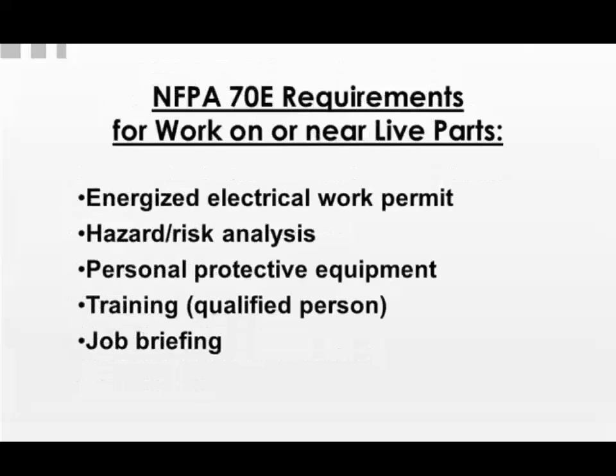So for NFPA requirements for work on or near live electric parts, you have to have an energized electrical work permit. You have to conduct a hazard risk analysis with all the parties involved. You have to make sure you have the right personal protective equipment on. You have the right training, so a qualified person, and you have to do a job briefing. So a lot of steps need to be involved and should be involved. Don't shortcut any of these steps. Not only are you violating the consensus standard, but you're putting your employees at significant risk and opening up potential very serious injury or fatality or multiple injuries or fatalities.